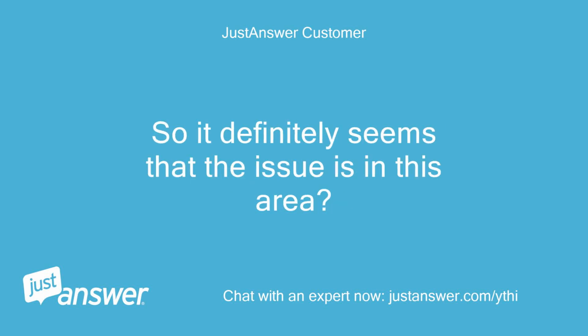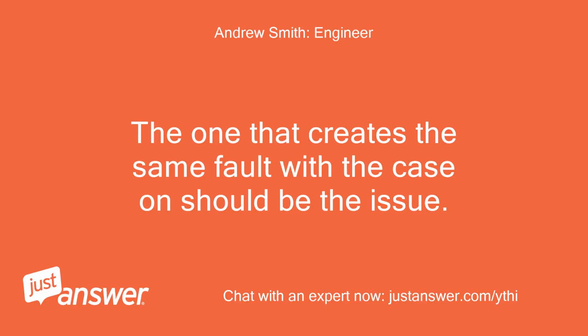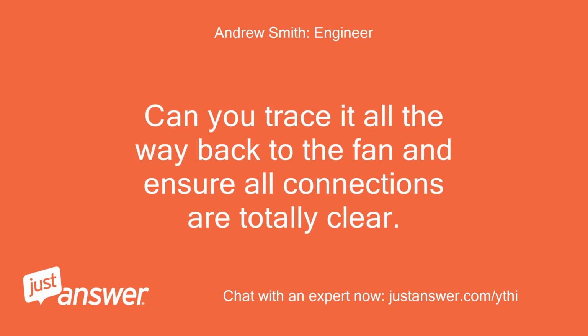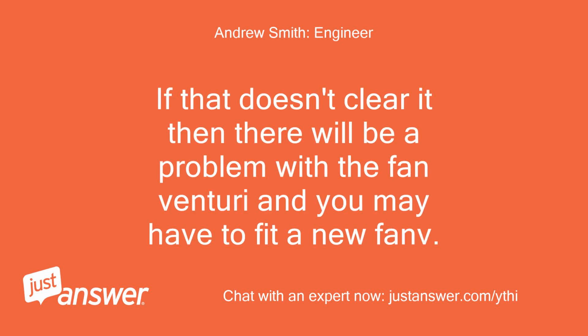So it definitely seems that the issue is in this area? The one that creates the same fault with the case on should be the issue. Can you trace it all the way back to the fan and ensure all connections are totally clear? If that doesn't clear it, then there will be a problem with the fan venturi and you may have to fit a new fan.